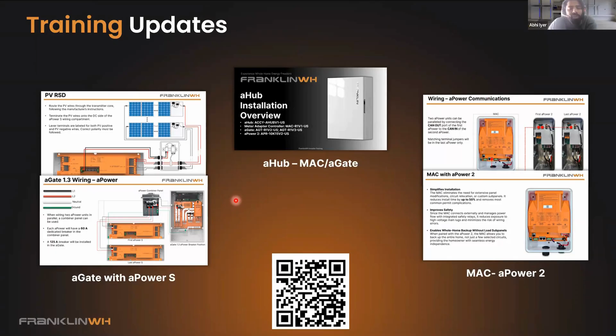to bring up? There was a question about the 15 amp continuous and what happens above 15 amps. 15 amps on the IMP? Yeah. So if you have modules which have IMP in excess of 15 amp, we are going to be limiting it to the 15 amps. So we have a few bifacial modules or larger modules which have 17 or 18 amps. Again, at that point, all you get access to is going to be 15 amps. So it's going to be limited by the MPPTs here.